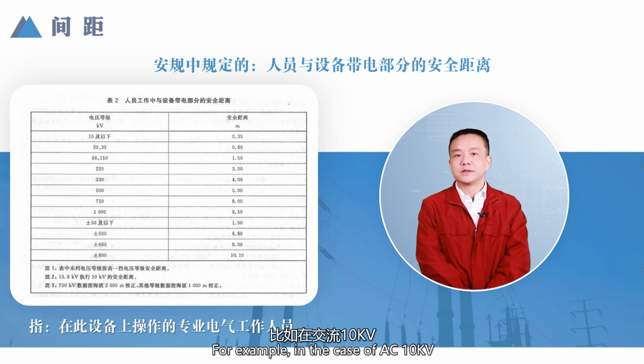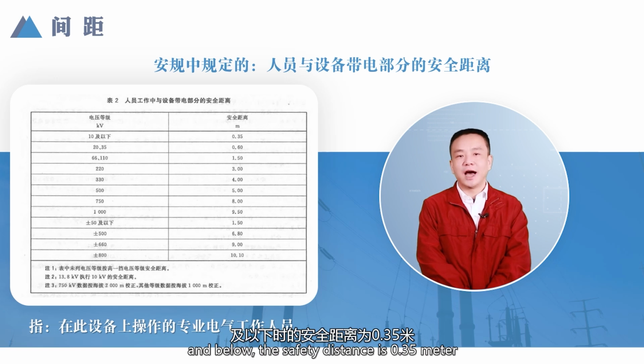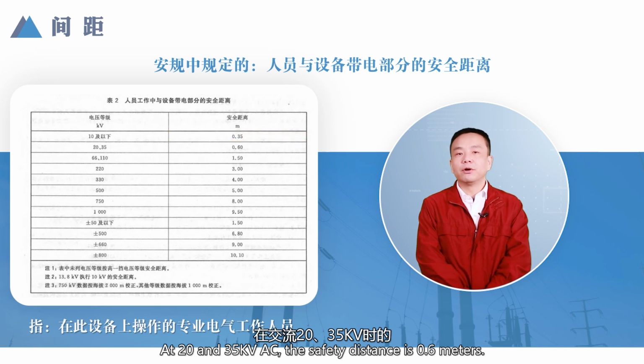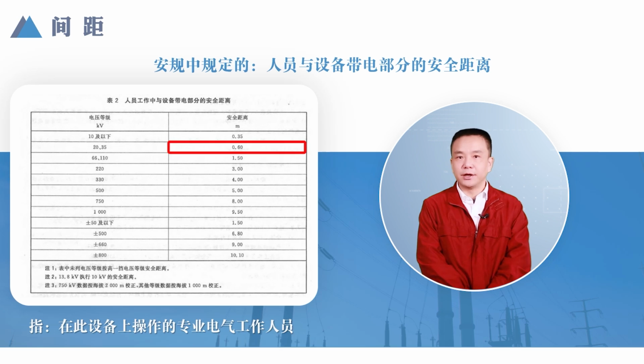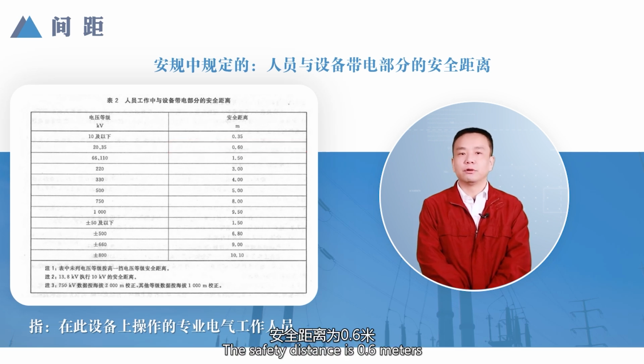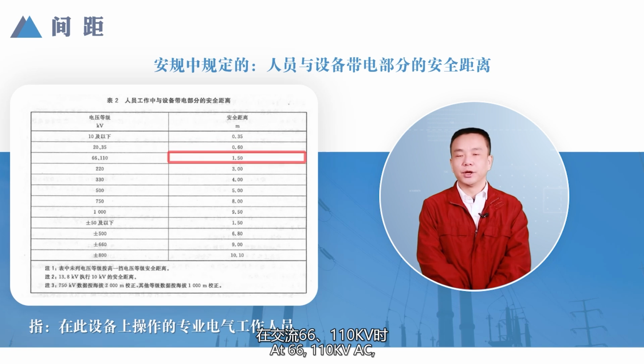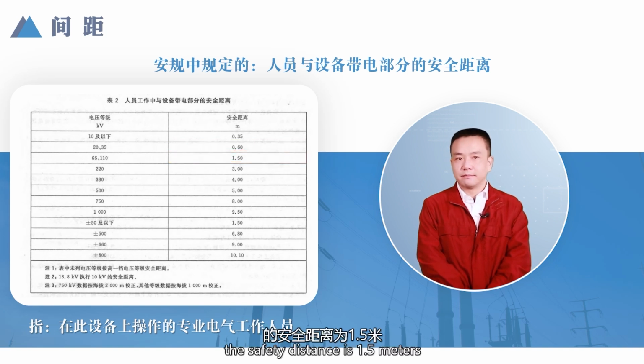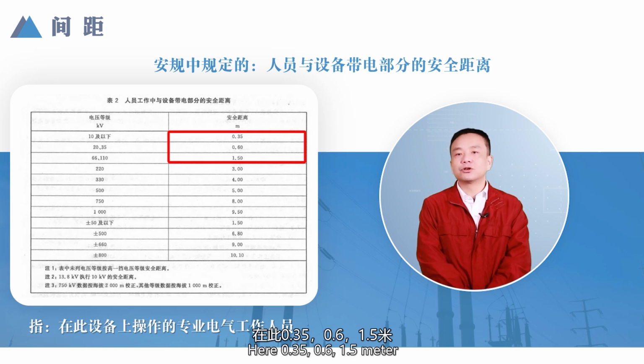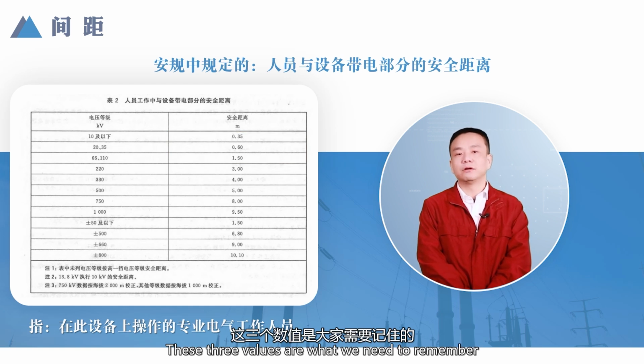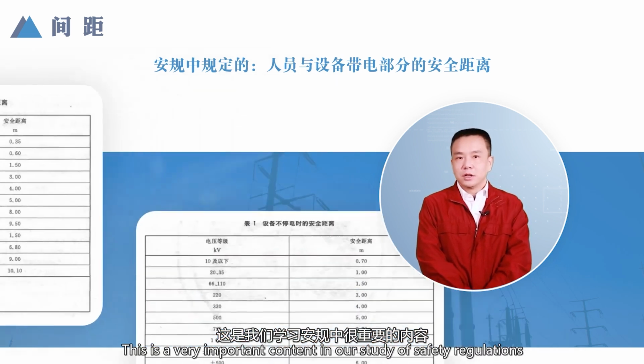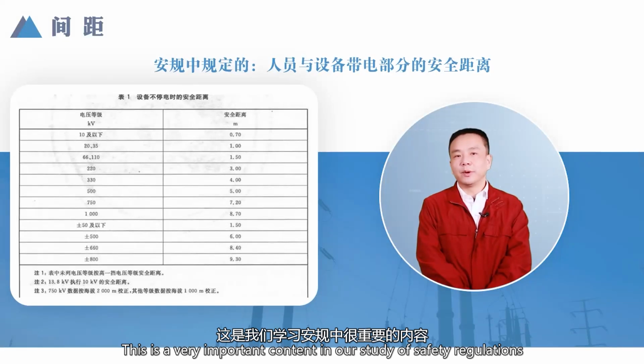For example, in the case of AC 10 kV and below, the safety distance is 0.35 meters. At 20 and 35 kilovolts AC, the safety distance is 0.6 meters. At 66, 110 kilovolts AC, the safety distance is 1.5 meters. Here 0.35, 0.6, 1.5 meters. These 3 values are what we need to remember. This is a very important content in our study of safety regulations.